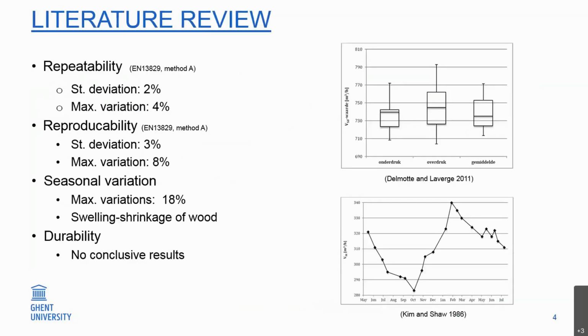In literature, we found a study by Delmotte and Laverge, which Valerie already mentioned, testing the measurement uncertainty under both repeatability and reproducibility conditions. For the first case, 10 tests were performed on the same building by the same operator using the same test equipment.